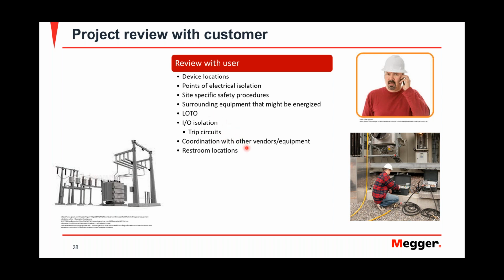IO isolation, your trip circuits. We're going to talk about test switches. Knowing which points on your test switch go to the trip circuits, and isolate your trip circuits before you do anything else. Coordination with other vendors. Usually when there's a shutdown, you're not going to be the only game in town. There's going to be other guys out there doing different things, different vendors. You got to coordinate with that.